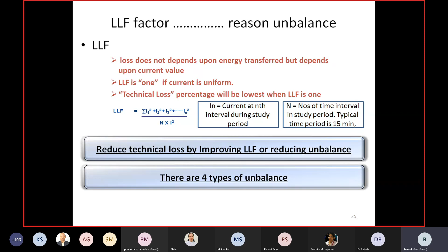And definitely we have the lowest technical losses. We know why technical losses are more - if there is non-uniformity, the technical losses will be more. This is the data we keep getting online, and wherever there is imbalance, we make it balanced. You cannot have exact equality, but try to make them as equal as possible. Keep computing your standard deviation - if it's high, bring it closer to the average value.